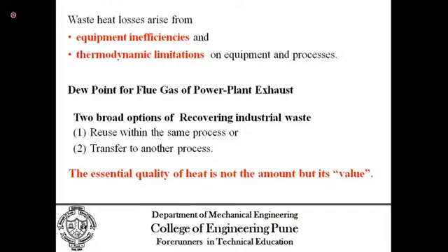We may have tons of exhaust gases with us, but if the temperature, maximum and minimum, is hardly 40-50 degrees Celsius, then we can say that it is a low grade energy. But if we have pressurized hot water with delta T very high, latent heat very high, then it can be graded as a high grade of energy. Always the question in a designer's or engineer's mind must be whether the energy is available in high quality or in high quantity. Important is its value.